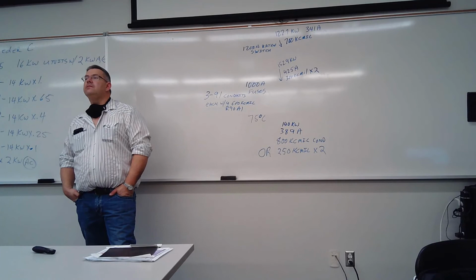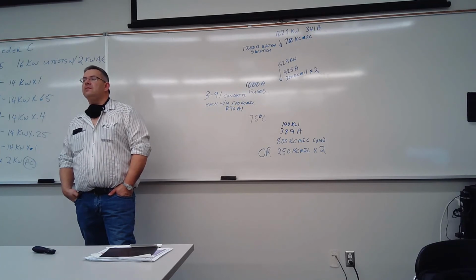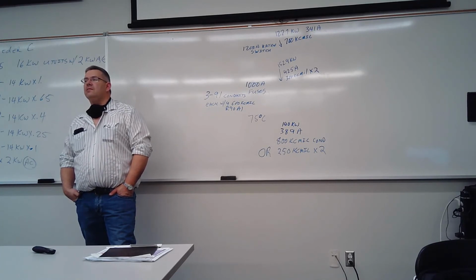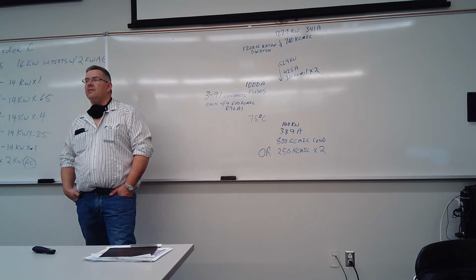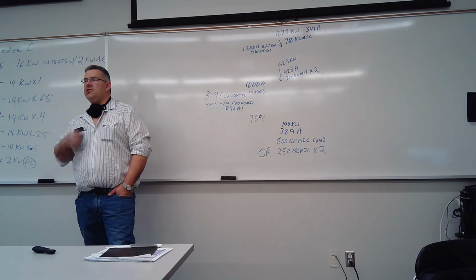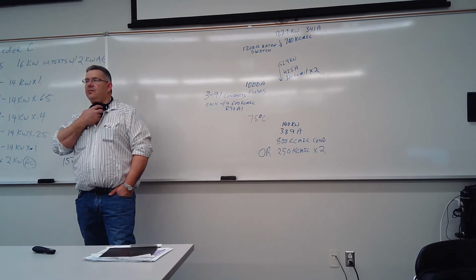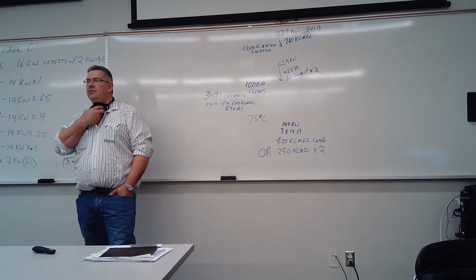From one test or whatever, one of the questions is calculate the minimum capacity for each conductor with a maximum load of 600 amps, and non-linear loads account for 50 amps. Where did you see this? I think it's one of the quizzes or whatever. Is there one? Did I miss that?